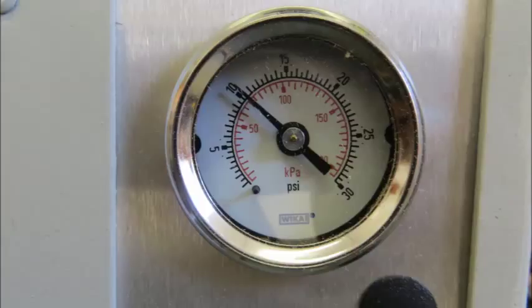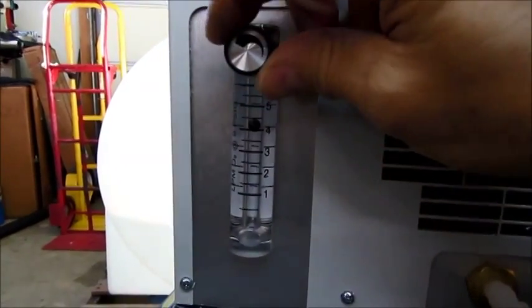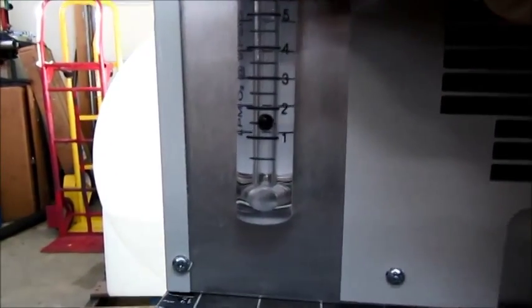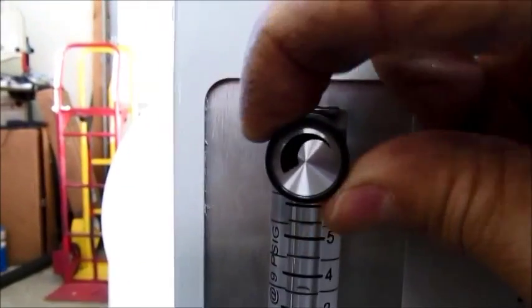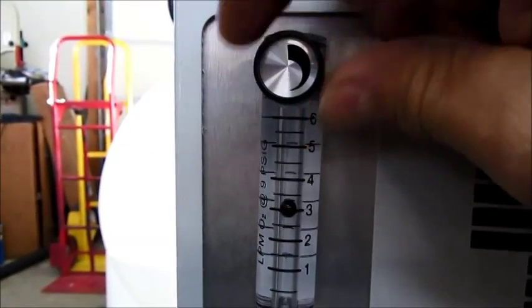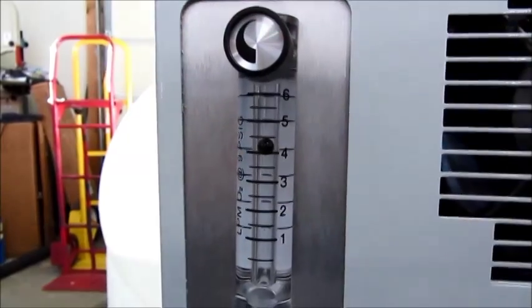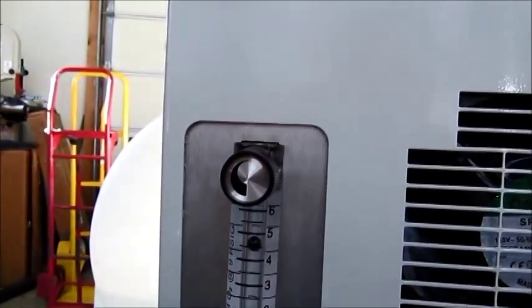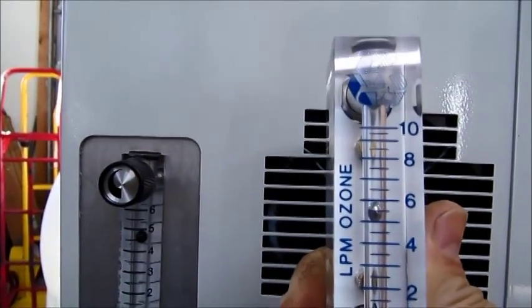Then we'll go to the left-hand side of the unit and look at the flow gauge with the flow adjustment. Turning it clockwise shuts down the flow, and turning it counterclockwise opens it back up. We want to set it to about 5.5 liters per minute as measured on our flow gauge.